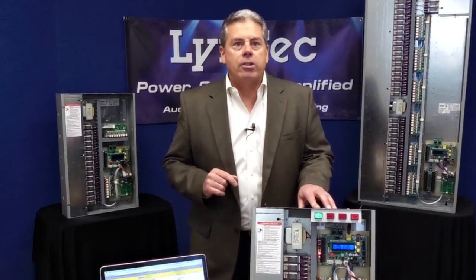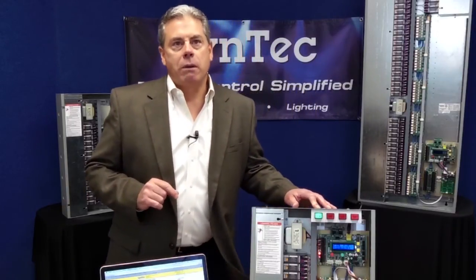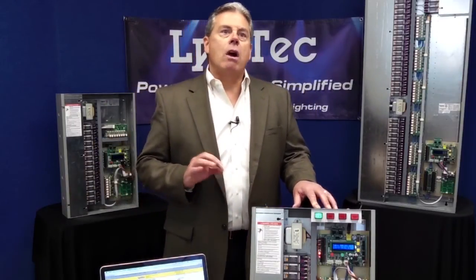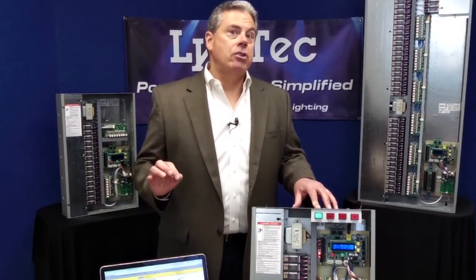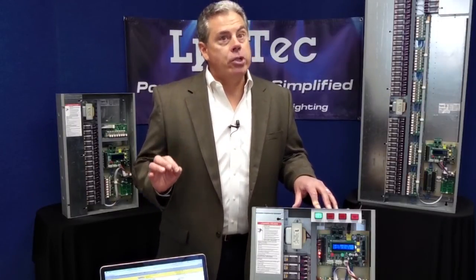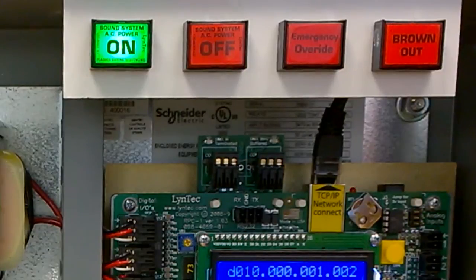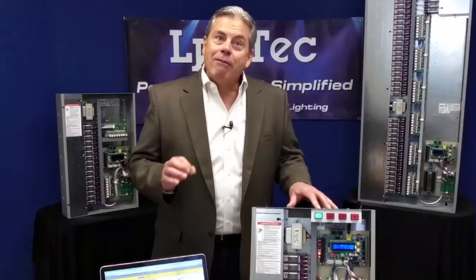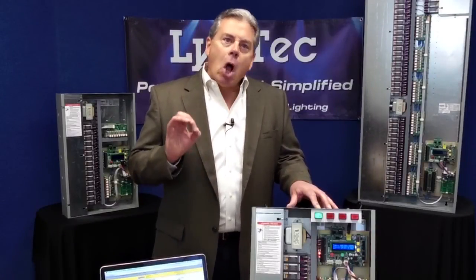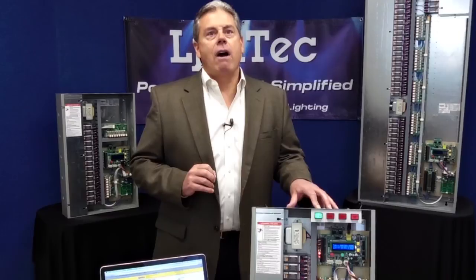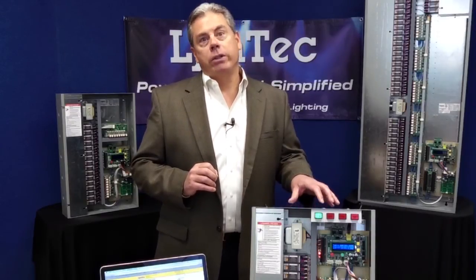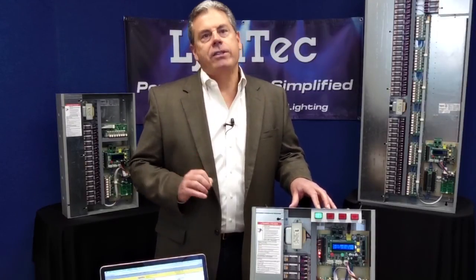The RPCR also offers multiple built-in global commands. These global commands work across zones to automatically shut selected circuits off on command. This is our load shedding feature. Or we can automatically select individual circuits to turn on, for example, as needed for emergency egress lighting. And we have a brownout feature that can be added that will automatically turn your selected circuits off in case of a power outage or an undervoltage condition, and that protects your sensitive equipment.